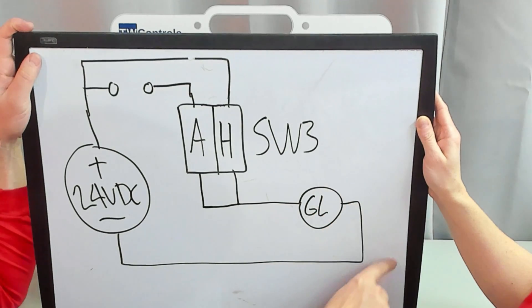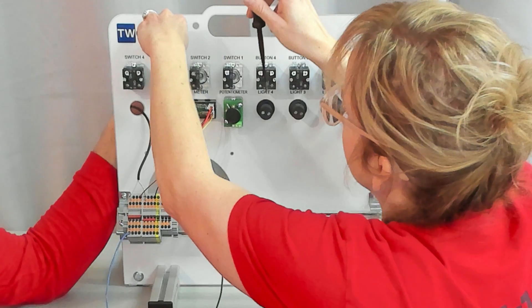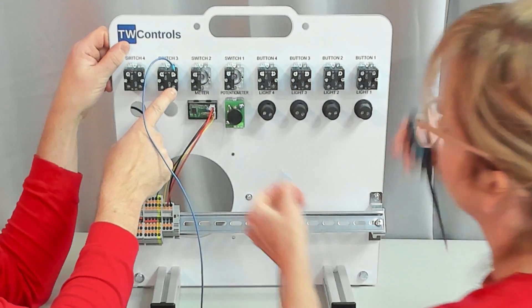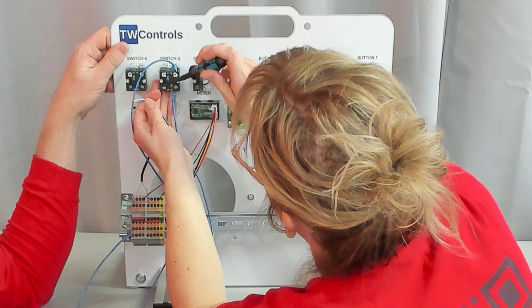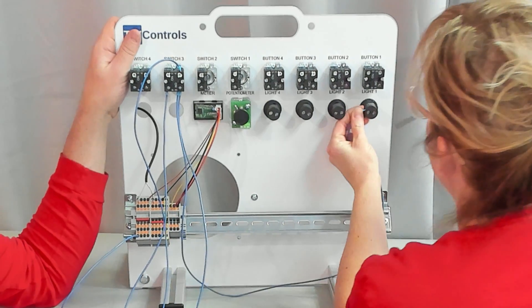Take a wire from the green light to the minus. Take a wire from the plus 24 volt, and I'm going to switch switch three to the left so we can make sure which contact is moving. We're going to take it into the top of the right contact. Now take two wires underneath the other side of the hand contact — take one of those wires to the bottom of the auto contact, and this is our jumper.